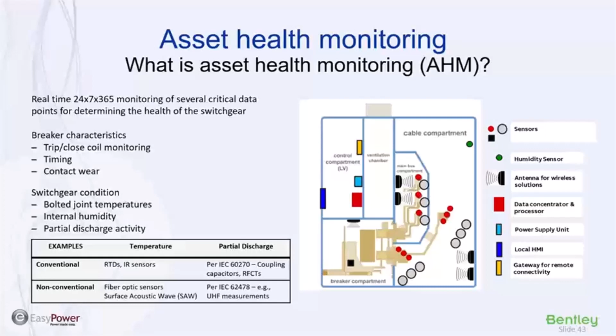Then finally, asset health monitoring. What we are concerned with here is monitoring the performance of the breaker or monitoring the condition of the switchgear. So bolted joint temperatures, humidity, partial discharge. And then, like I said before, there are multiple technologies that are available, right? All are effective. It really depends on your preference on a specific application, okay? So again, when you use these technologies, there is obviously an added upfront cost.